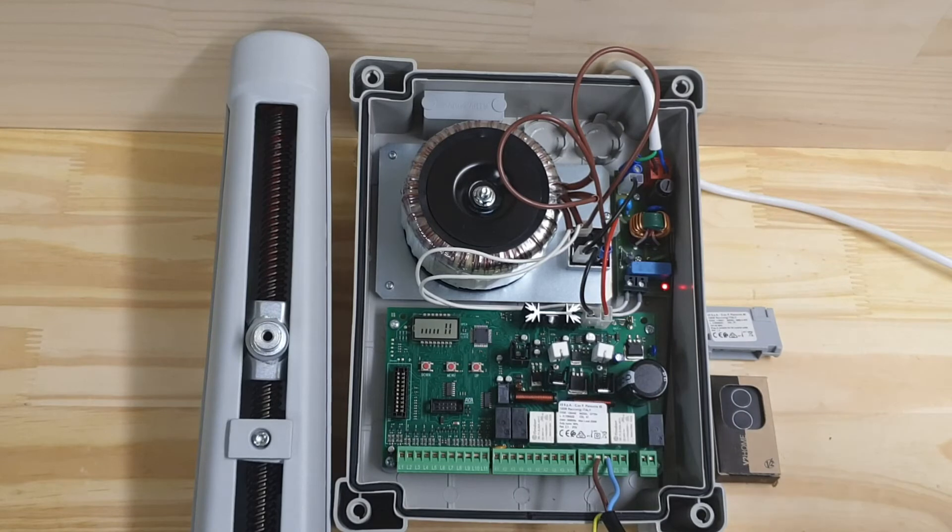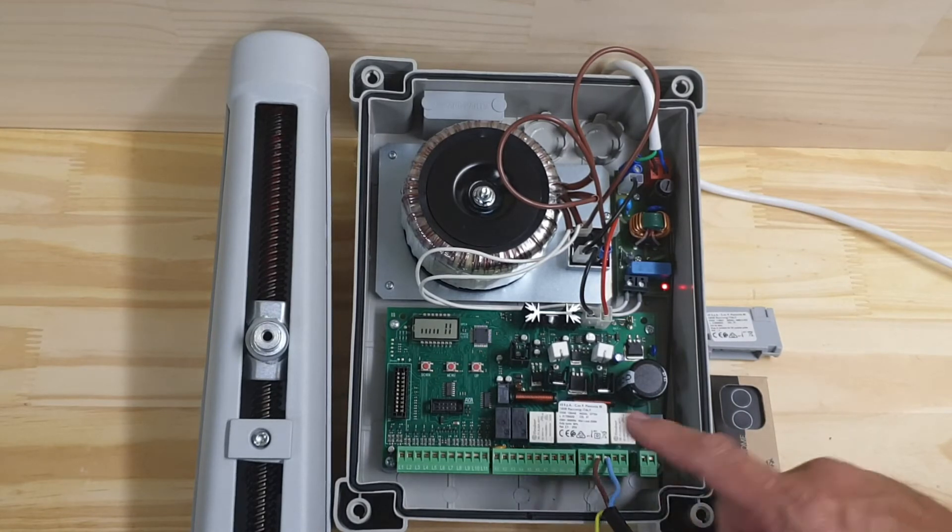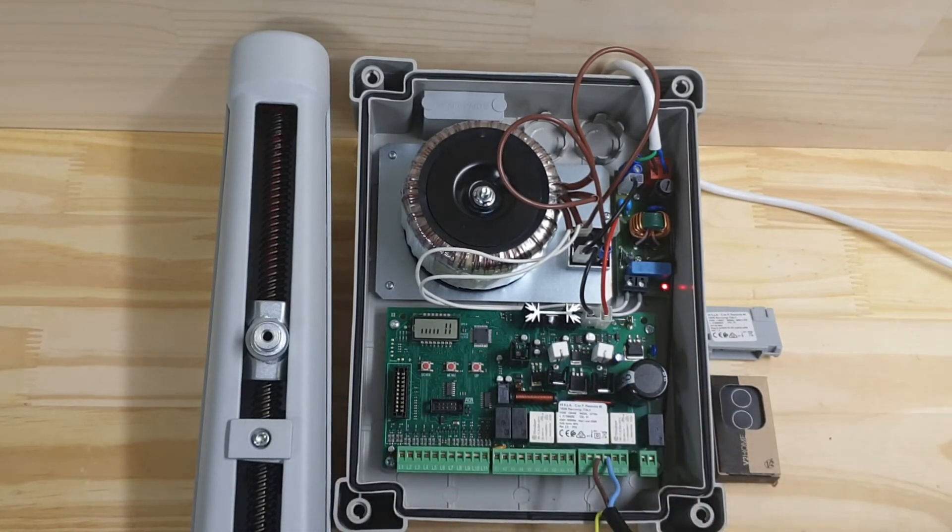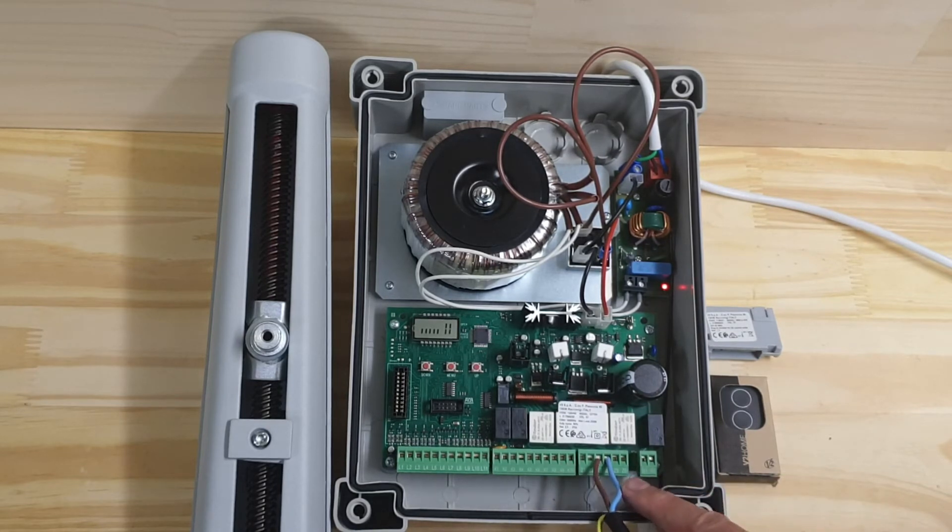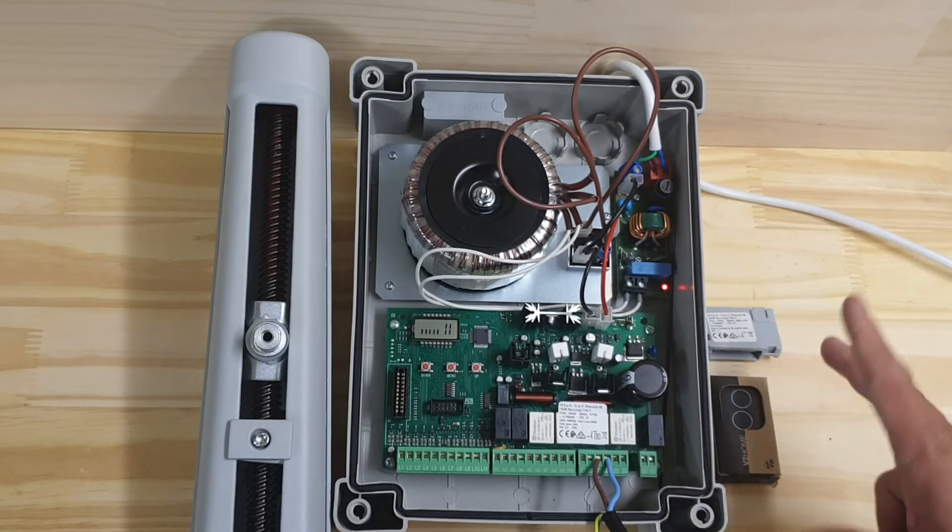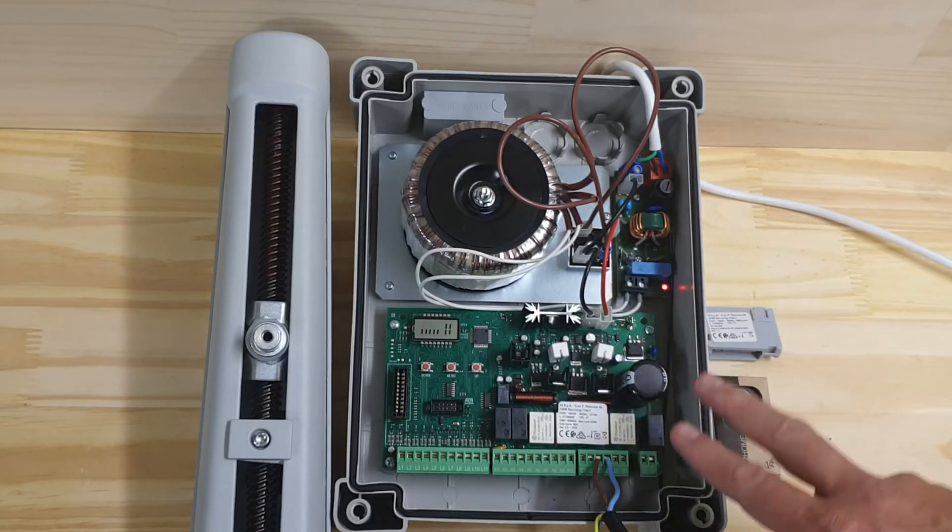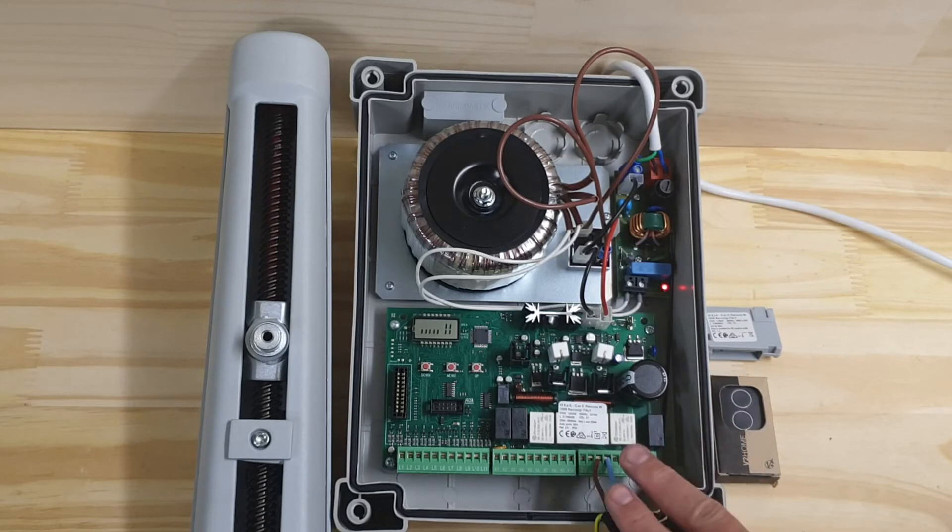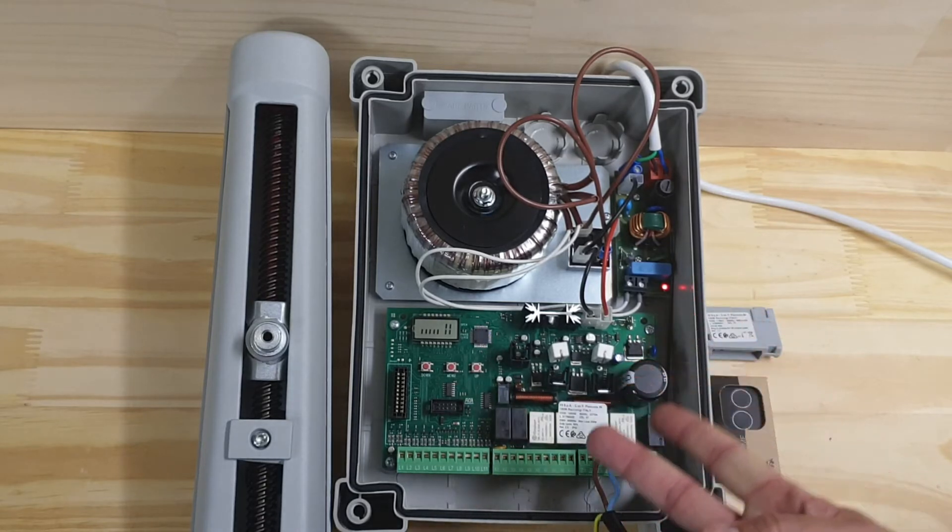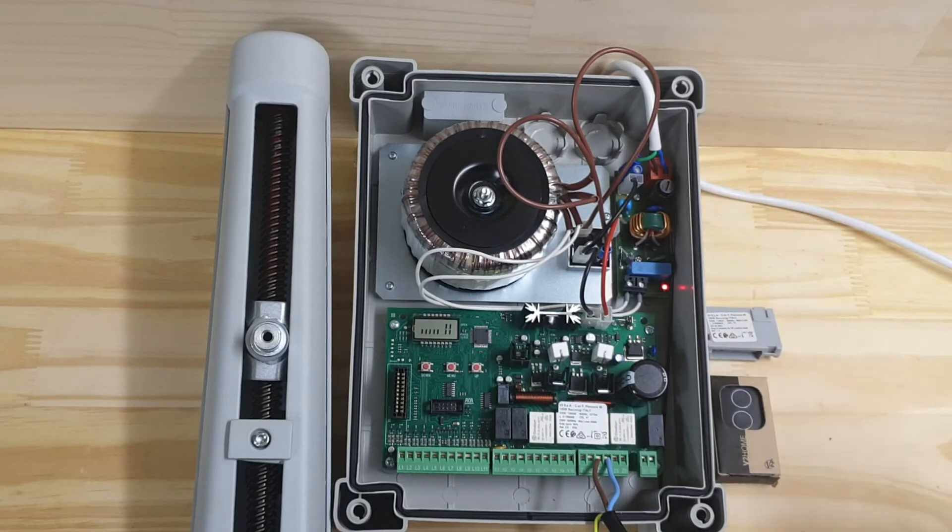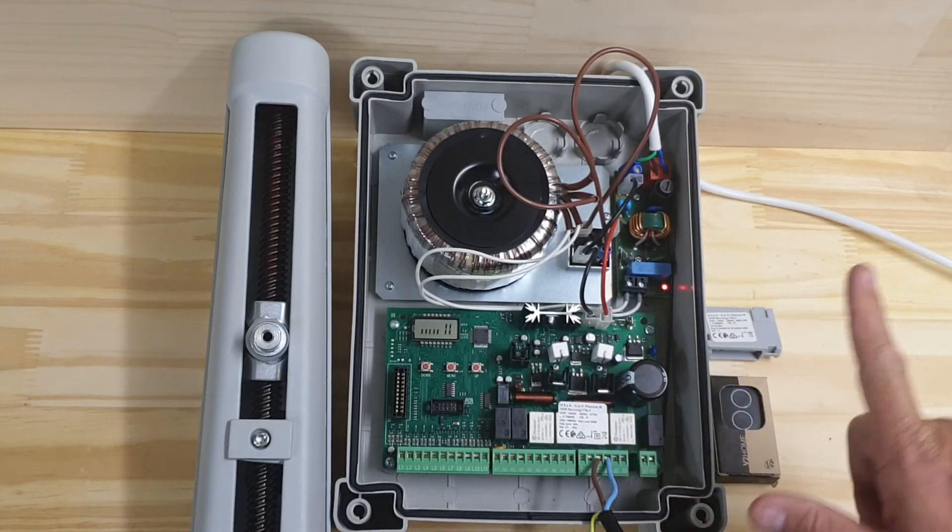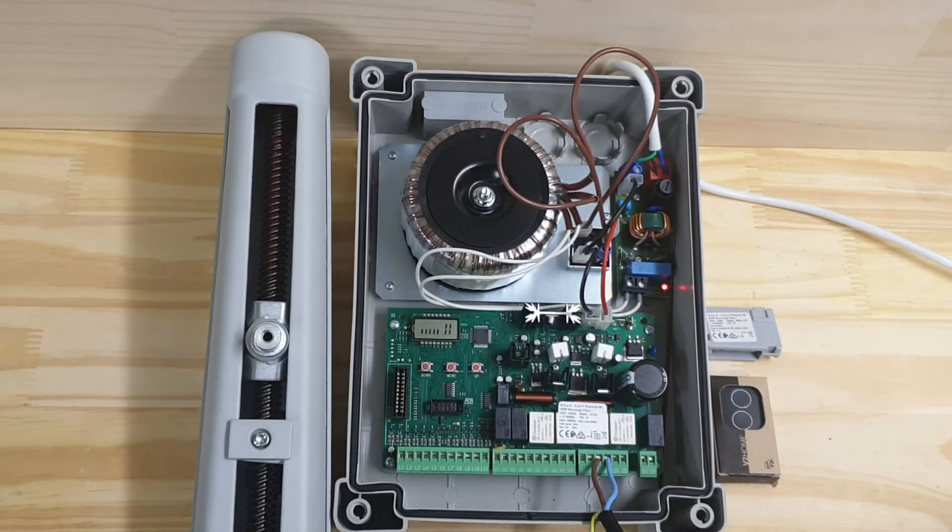The next thing I want to do is wire my motor. So this is motor 1, and I'm only using one motor, so I've wired into Z3 and Z4, which is just positive and negative for 24 volts. If you found that it was running the wrong way, you can just swap those two over and that will change the polarity and change the direction of your motor. But because I'm only running one motor, I want to turn motor 2 off.